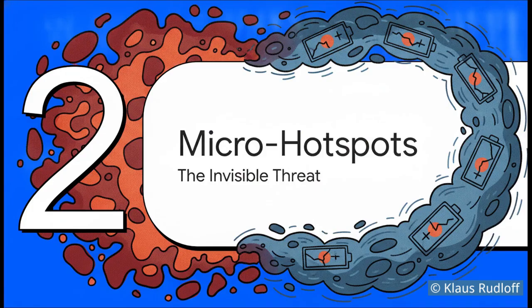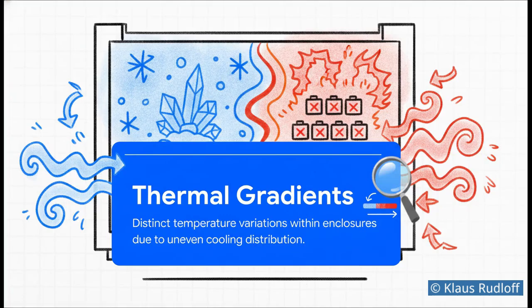Which brings us to Section 2, hidden micro-hotspots explained. This lack of uniform cooling leads us straight to the invisible threat quietly destroying grid assets. So what happens is we get distinct thermal gradients forming because of that uneven airflow. A thermal gradient basically means we've got distinct, measurable temperature variations arising within the exact same enclosure. One side of the rack is nice and cool, while another pocket is literally baking. This isn't just some minor inefficiency we can brush off; it's a fundamental shift in how the battery system operates, heavily impacting very specific vulnerable areas of your system.